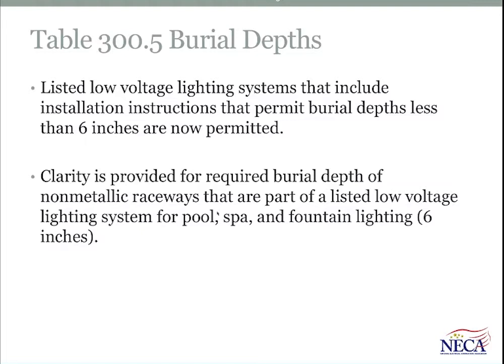So what we have is a clarification, and you'll see a superscript note that follows the table that's actually part of the table as a rule, which clarifies that the listed low voltage lighting system installation instructions can take precedence, and you don't have to follow the minimum requirements in the table if the instructions say otherwise. So those low voltage lighting systems that may be installed for landscape lighting, for example, you can follow the installation instructions and you're not tied to the values in the table.